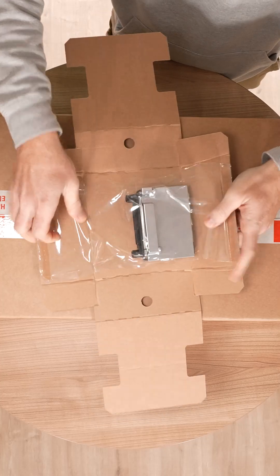What I can see is that's a module for the new MX system, right? Right. Can you give us an idea what it is exactly? This is an EtherCAT power output, so we have two channels each with two M12 connectors. One is for EtherCAT and one is for 24 volts, while we have one pin that's switchable and one pin that's not switchable. So a classic module for decentralized peripheries in the field. Correct. You could use an EtherCAT valve manifold for example, or our EP boxes as remote IOs. So it's a standardized module that you can connect to several components in the field.